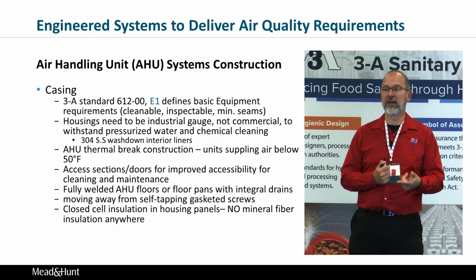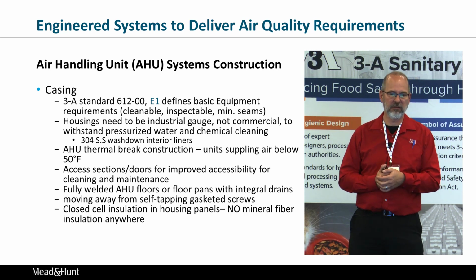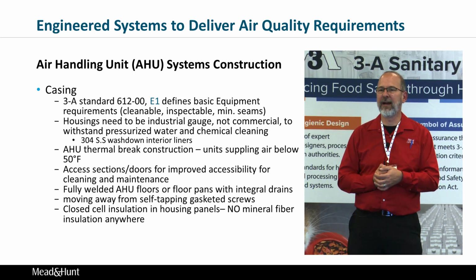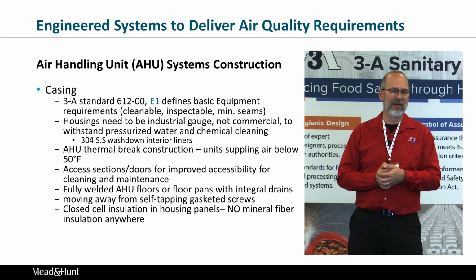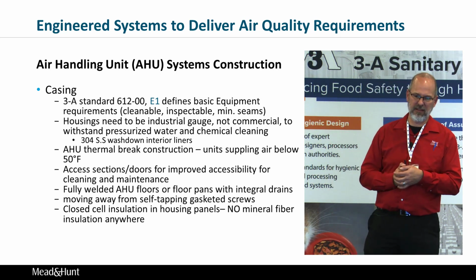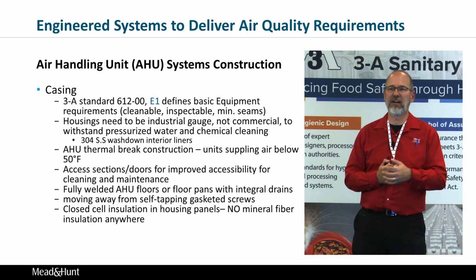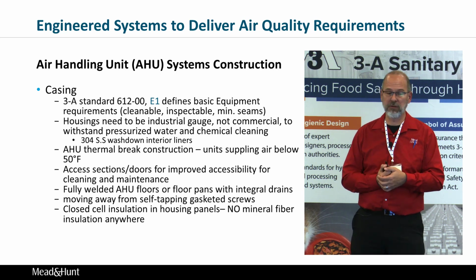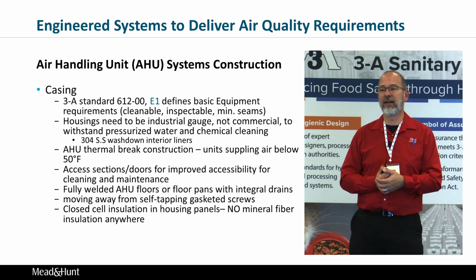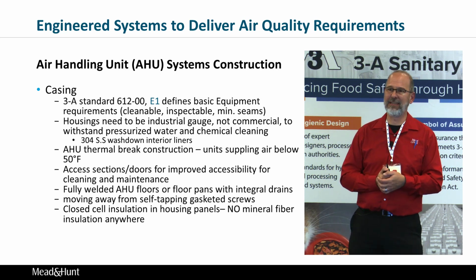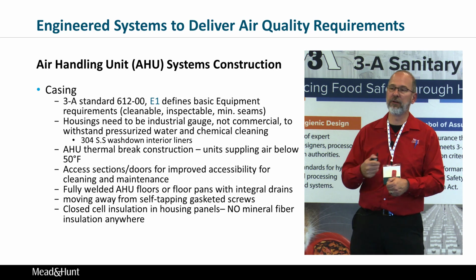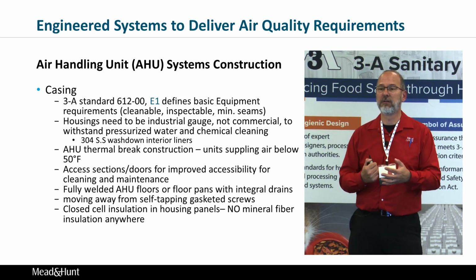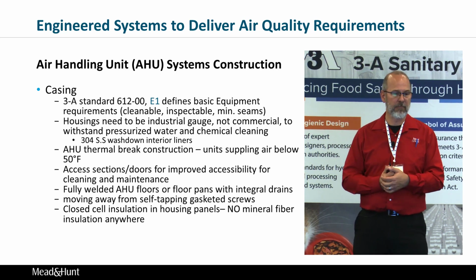It needs to be cleanable, inspectable, with minimum seams. You can get food-grade air handlers designed to do that. The housings need to be industrial gauge, not commercial. The skin thickness on the outside and inside of the unit will be thicker than a commercial unit would be. And typically the inside liner of that air handler will be stainless steel and designed to shed water. So if you go in there and clean it out with chemicals, it'll all drain.